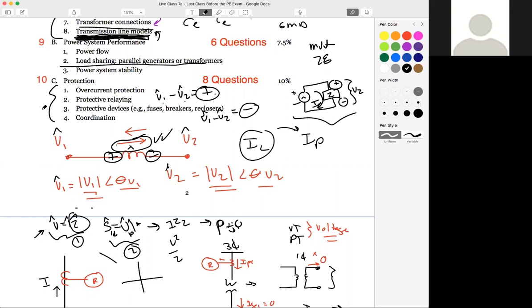Protective relaying, same goes there. Protective devices, also a good overlap of the NEC there. We talked about that in that one class, be comfortable with TCC diagrams and curves. Same thing with coordination, right? You never want something upstream to trip for a downstream fault. You want your TCC curves to be lined up pretty properly.